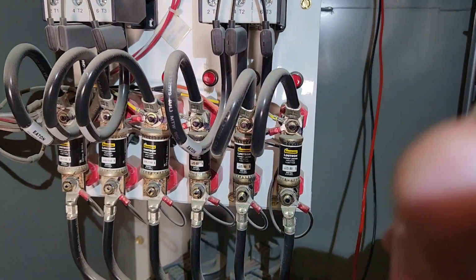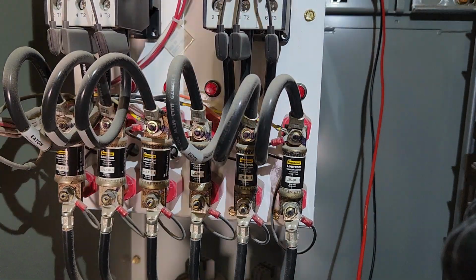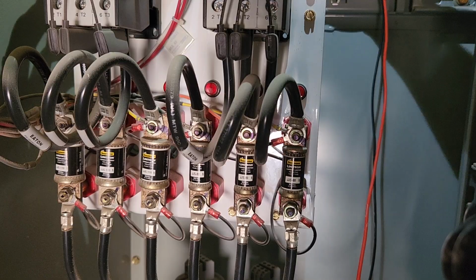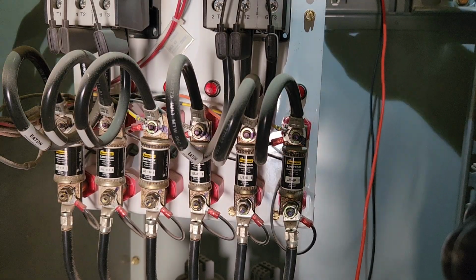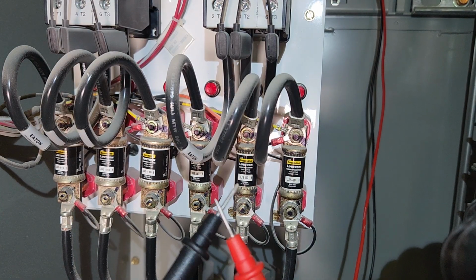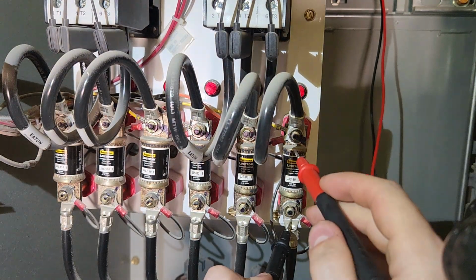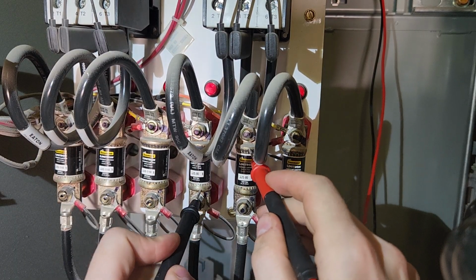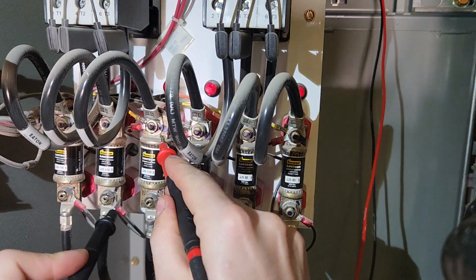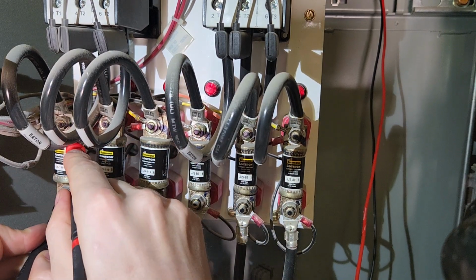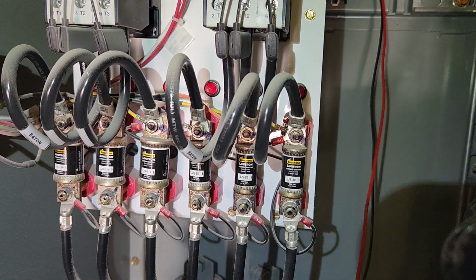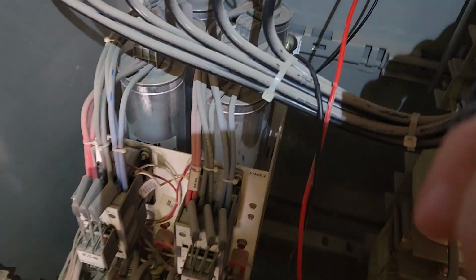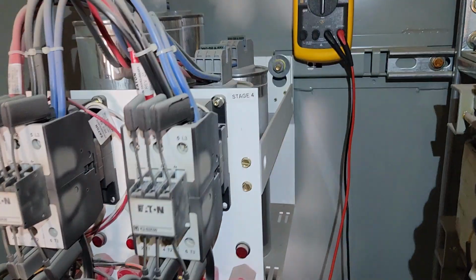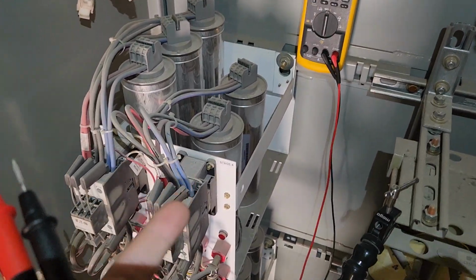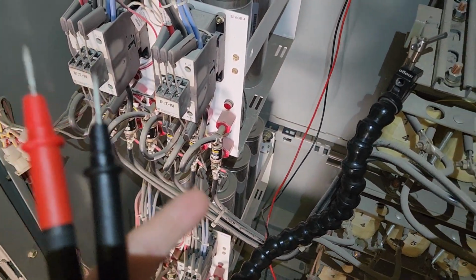I could have checked these fuses as well. These are fuses for each of the capacitor setups. I'll just go to continuity and verify here. These should all be good. And that's all good. Then we got another set down here that I can check. And just kind of an FYI, let me take this off. So we walked through checking capacitance on each of the capacitors, checking fuses on each of the capacitor banks.